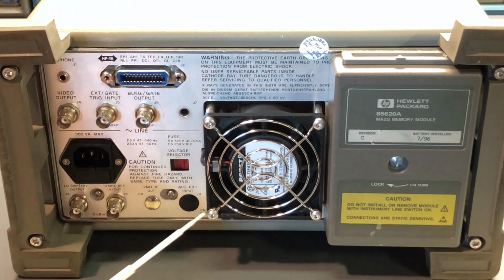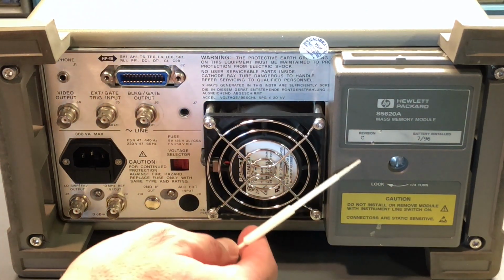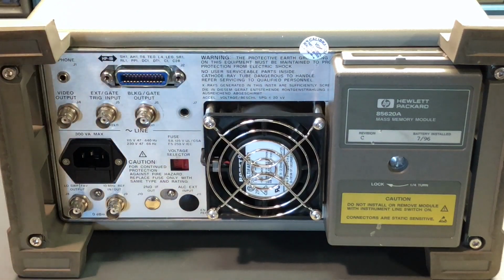Cooling fan, of course, and then right here, this is a mass storage module. It's an option. It plugs onto the back, and there's a slot right here where a memory card can be installed. By today's standards, the memory capacity of this system is pretty low, but back in the day, it was pretty cutting edge. And it's basically for storing traces and other operating parameters that the instrument has.